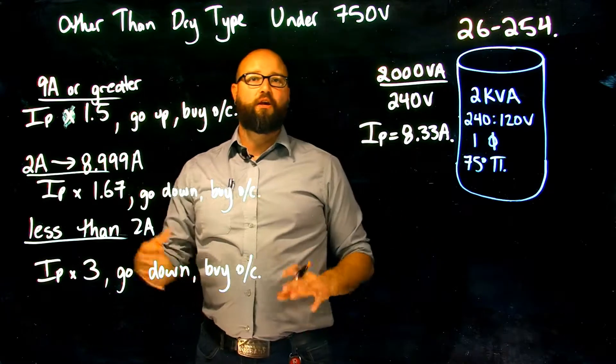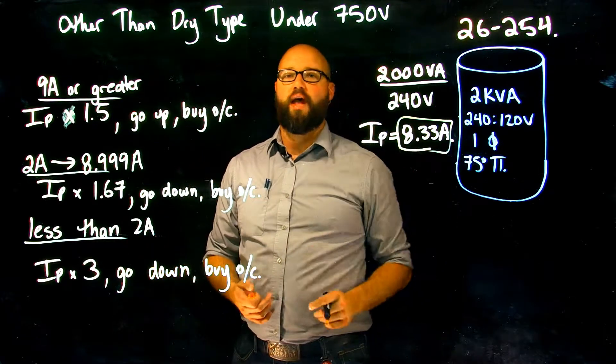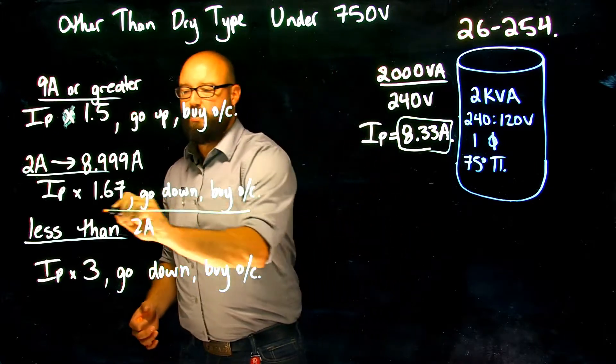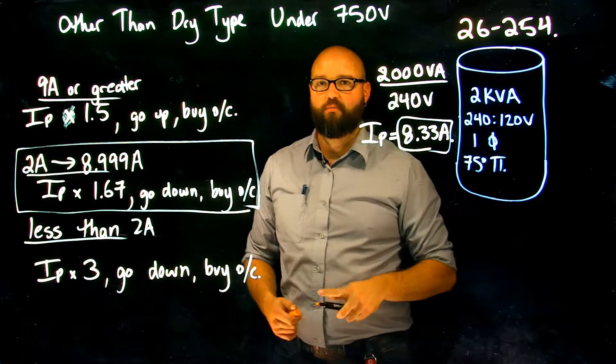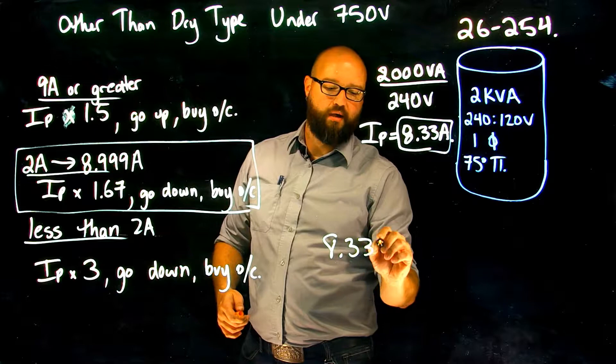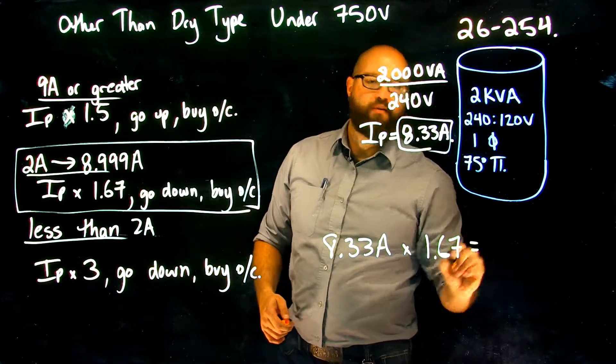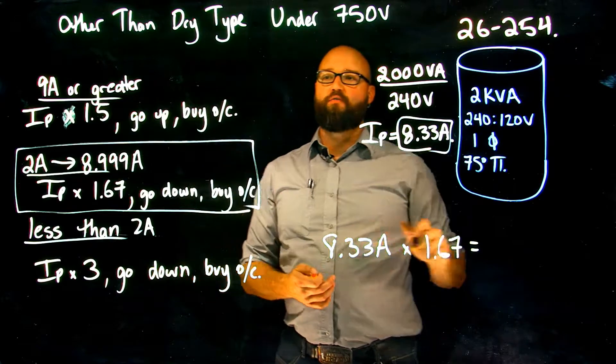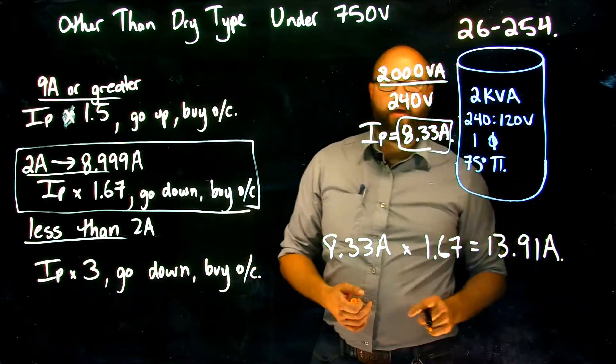We have three individual choices here depending on what the rated primary current is. In this case, because we are looking at 8.33 amps as our rated primary, this right here becomes our multiplier. Our 167 percent is our multiplier. So we're going to take our 8.33 amps, multiply by 1.67, gives me a maximum rating of my overcurrent of 13.91 amps. I am not allowed to exceed that.